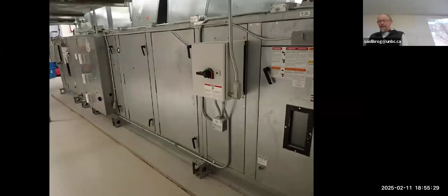It is served for heating, ventilating and cooling the school by an all-electric air handling unit, which heats and ventilates the entire school in conjunction with a couple of heat recovery ventilators. It's hard to know what this is doing, but the airflow is from right to left. So in comes the return air through here. It is diverted by a set of dampers that are sitting in here, and a certain amount of it is exhausted up through this duct. Then these dampers also determine how much air is going to be introduced from the outside air here. It comes through, runs through a bank of filters here, and then goes through 3 big electric heating elements, which heat it to the required temperature for whatever the school is calling for.